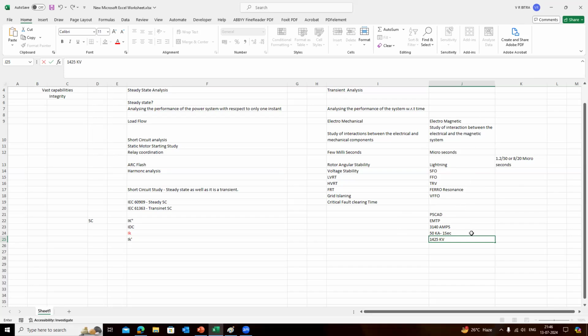The purpose of performing the study is to find out whether the surge arrestor is needed or not, and if required, how many surge arresters are required, where it is to be added, and what are the characteristics of the surge arrestor to select. For all other equipment, it helps find out the BIL, the basic insulation level or basic switching level. That's probably all about these EMT studies.